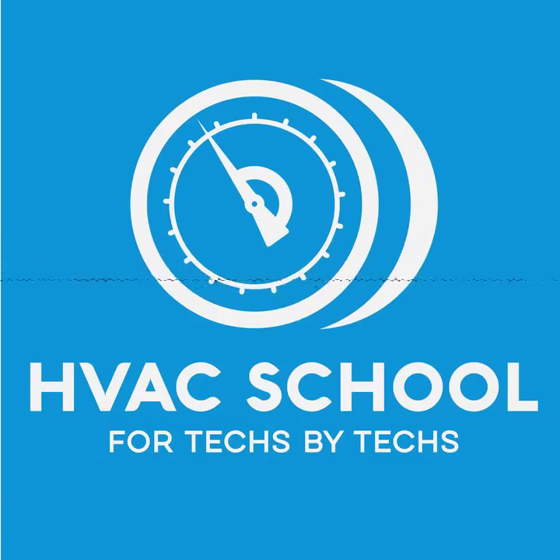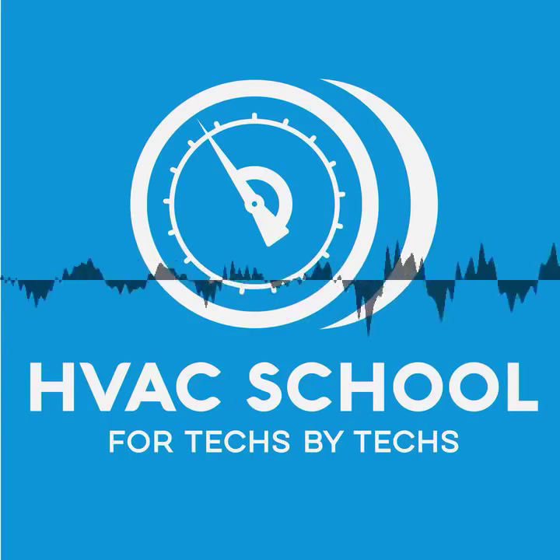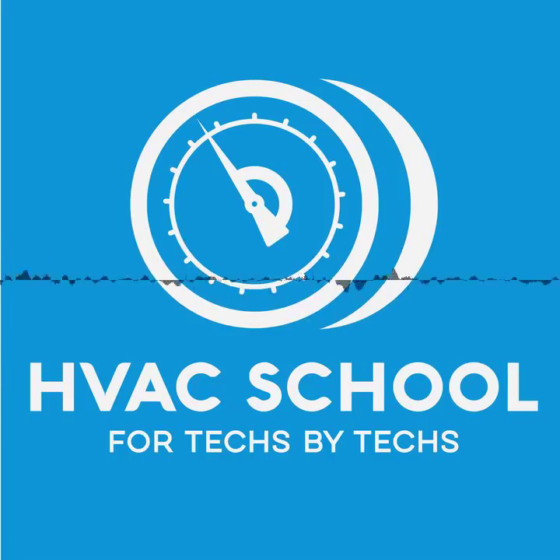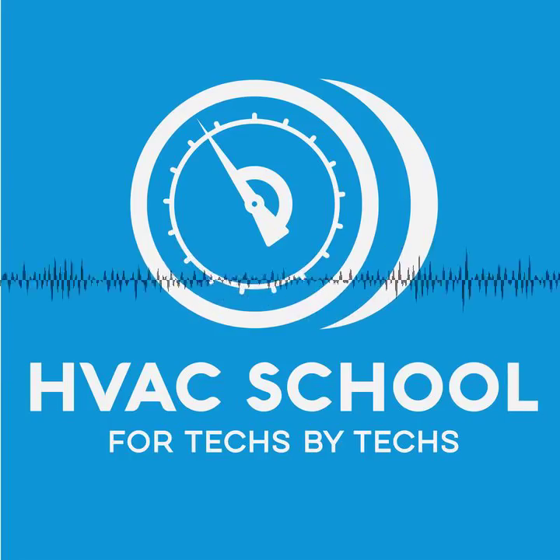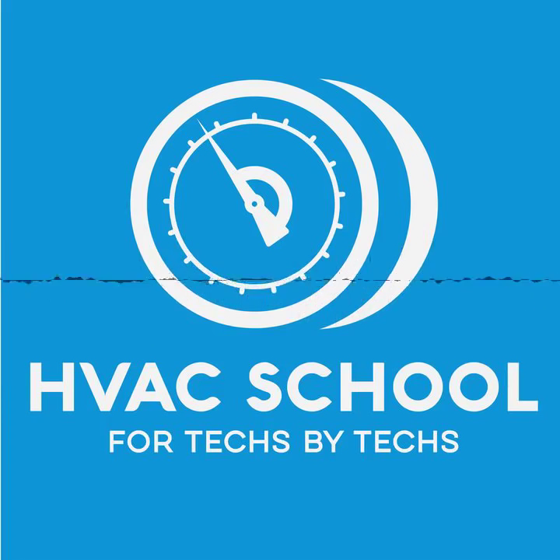True. To some extent, you have this problem also in air conditioning, but it's not as dramatic. If you look at, for example, superheat charging charts with fixed restrictions, when you see superheats in the high 20s and low 30s, what they're really telling you is the system is not at full capacity at that condition because of the lower head pressure. So in effect, you have the same situation where you're not moving as much refrigerant because of the changed compression ratios. But there, they do go ahead and give you a guide for charging. It's just not as dramatic a change as you have in the heating cycle.